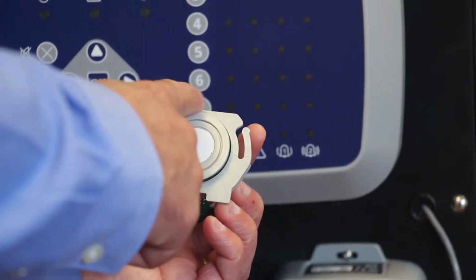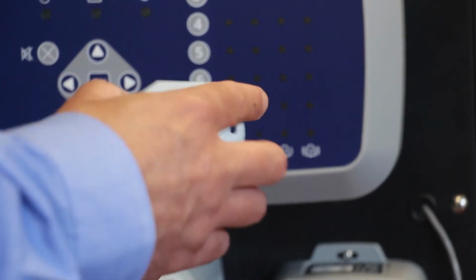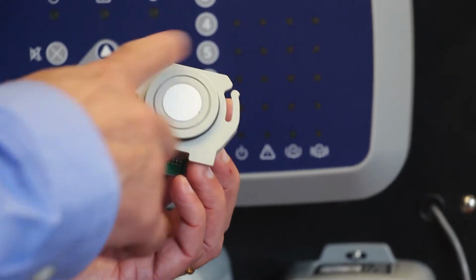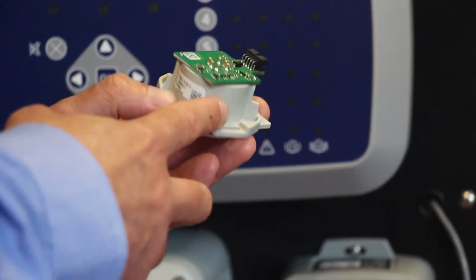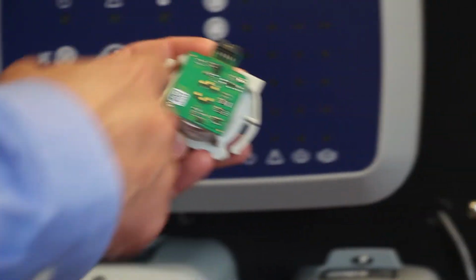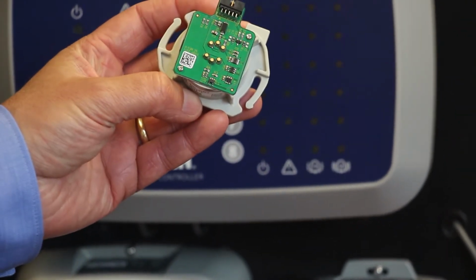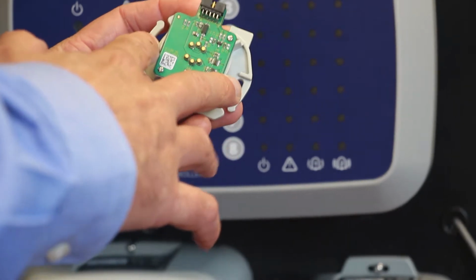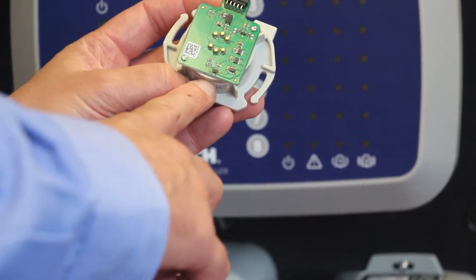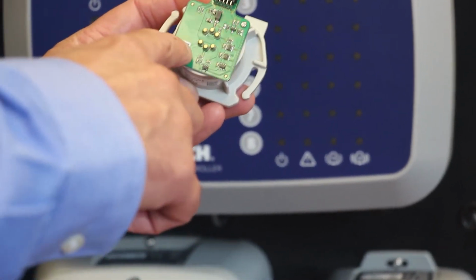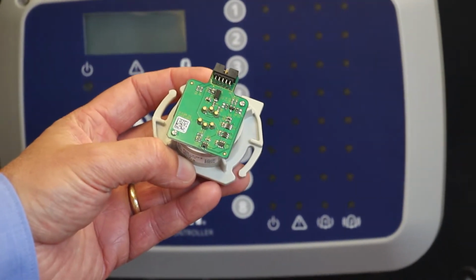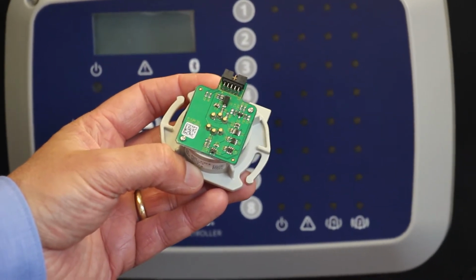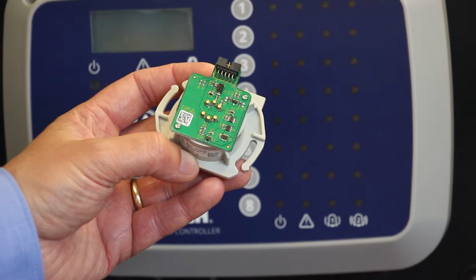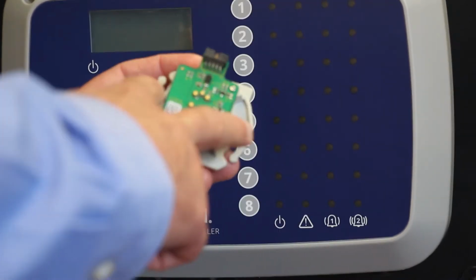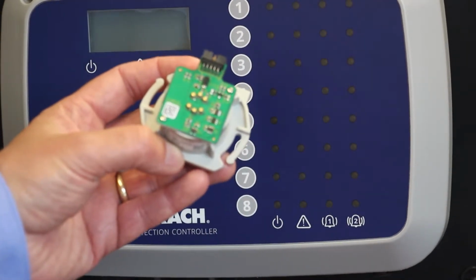As you can see, it's a fully formed sensor module with the sensor built into the unit. Each sensor module comes with its own PCB, and this PCB holds all of the calibration information, sensor information, what gas it's calibrated for, the sensor range, and the calibration history — all of that is held within this PCB.